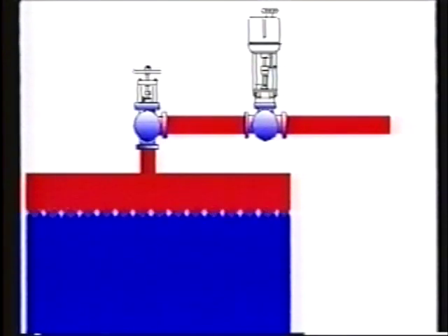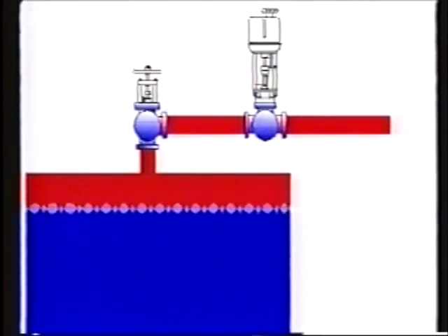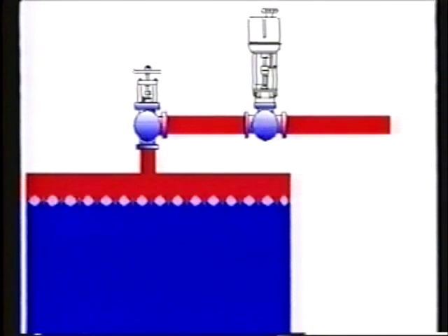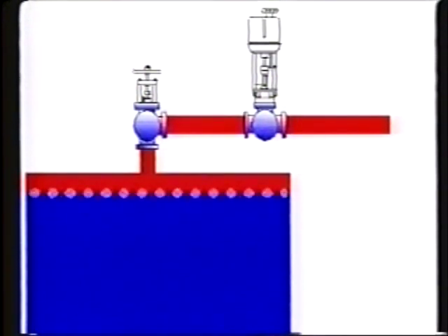The bubbles of steam expand under the reduced pressure, causing a rise in level which is not always apparent in the sight glass or inside the protection tube, both of which contain water without steam bubbles. If the steam demand is increased beyond the limit of the boiler's maximum steam generation rate, the effect can be spectacular as well as potentially dangerous.